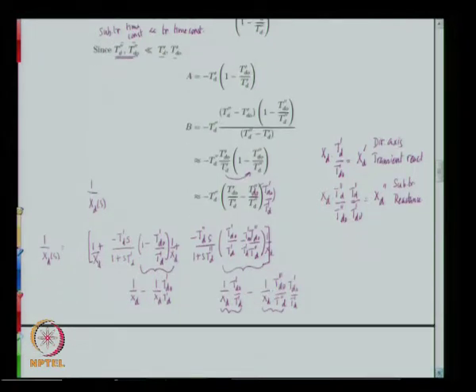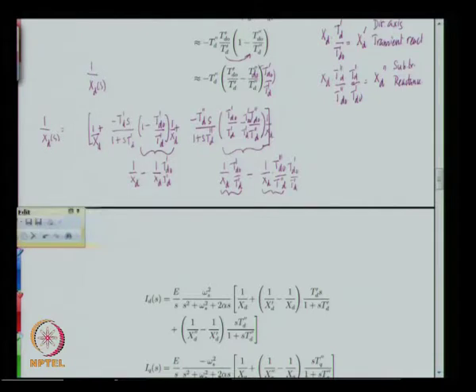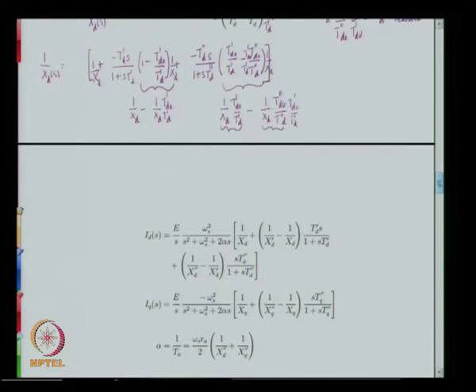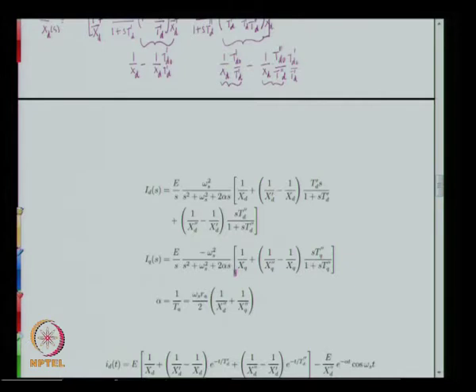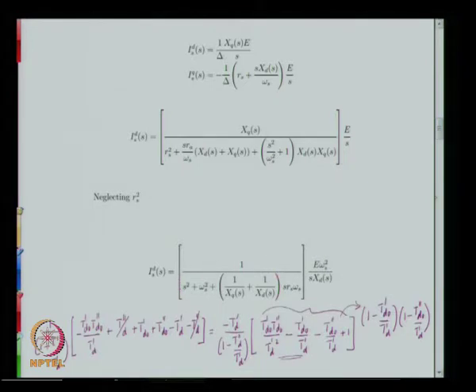So 1/xd(s) simplifies as we see: it is 1/xd plus (1/x'd – 1/xd)·s·T'd/(1 + s·T'd) and a further sub-transient term. Similarly, iq(s) can be written in an analogous form using the same elimination method. Both these expressions come directly from the expressions for id and iq derived from the matrix inversion.